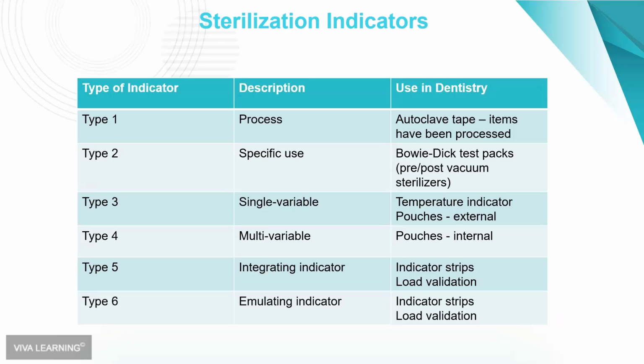So here we have the breakdown of what these indicators mean, what constitutes an indicator. So autoclave tape, again, is a type 1 process indicator. Items have been processed. I can look at a package and say, yep, it's been processed. It's likely, if my sterilizer is working appropriately and if it was loaded properly, that they're sterile, but that's not the indicator of sterility. A type 2 indicator is what's called a specific use indicator.